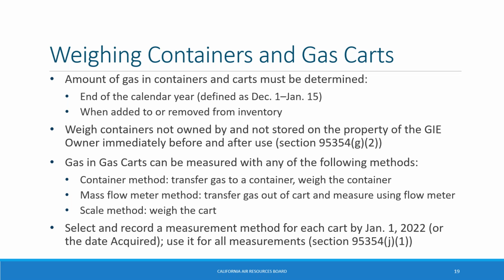Also, section 95354G2 specifies that gas containers not owned by and not stored on the property of the GIE owner, which are brought on site for use at the GIE owner's facilities, must be weighed both immediately before and after use. The amount of gas within the container when it arrived must be reported as added to inventory, and the amount of gas within the container when sent away must be reported as removed from inventory.